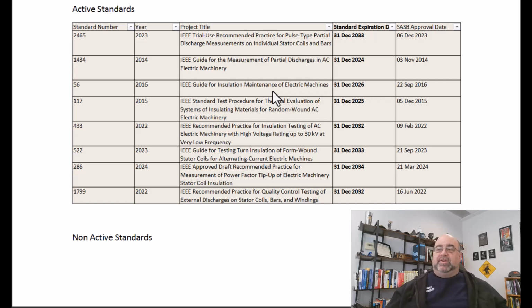My pushback on some of the discussion we had on releasing it had to do with the fact that somebody had mentioned something about if all the other tests passed and you slice up the sample bar, you open it up and you find a defect in there. Well, how can you condemn everything because it passed the test? And I had to remind everybody the visual inspections are more important than electrical tests. So that's kind of it.